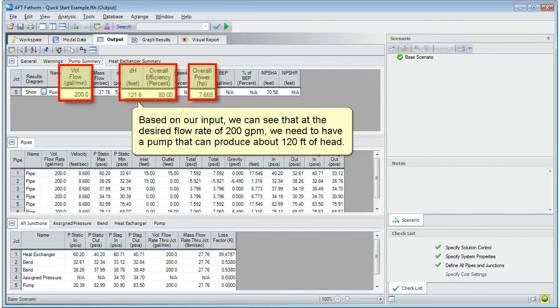Based on our input, we can see that at the desired flow rate of 200 gallons a minute, we need to have a pump that can produce about 120 feet of head.